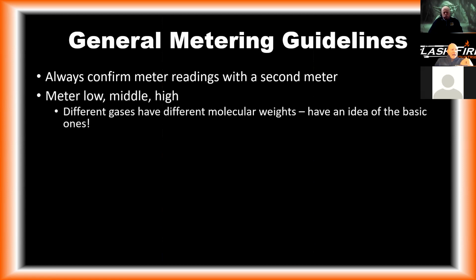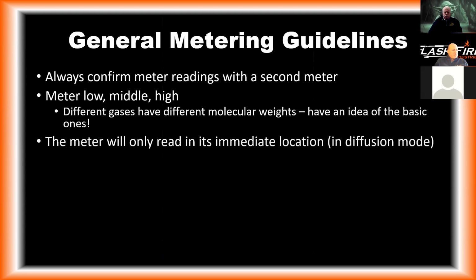We've got to remember that different gases have different molecular weights. Have an idea of the basic ones. So CO, you should know, is fairly neutral, maybe rises a little bit. Propane sinks; methane, natural gas, rises. So just have a decent idea of some of those basic ones. So if we have a natural gas leak on the first floor, am I more concerned about going above or below, versus propane? The meter, as it sits, is only going to read in its immediate location.